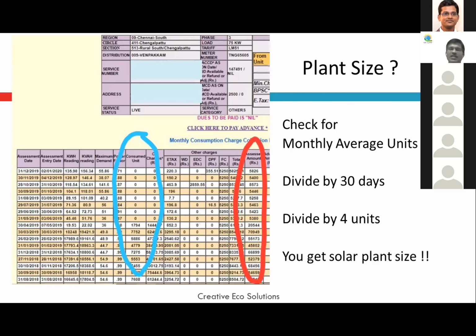Let's say for an office, I'll take 80% of the 25 kilowatt plant and install a 20 kilowatt plant to avoid excess export. If it's a residence, I'll take only 40%, since 40% is consumed in daytime and 60% at night — so I'll plan for only 40%.